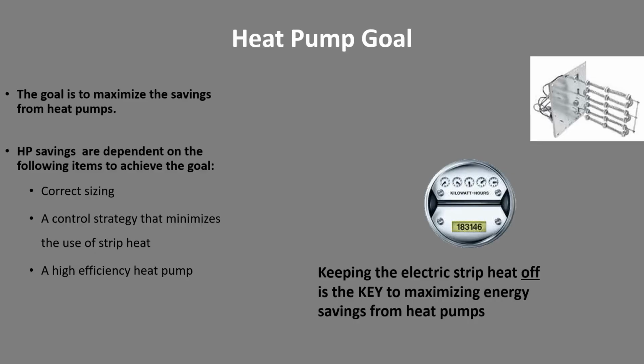Heat pump goal. Heat pump goal in PTCS is to maximize the savings from heat pumps. In order to do this, we need correct sizing, a control strategy that minimizes the amount of strip or auxiliary heat, and a high efficiency heat pump. Keeping the strip heat off is the key to maximizing energy savings.